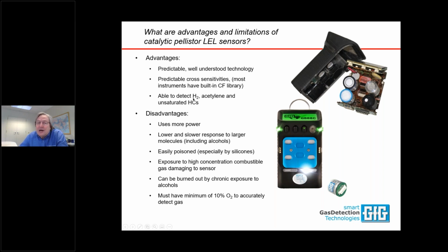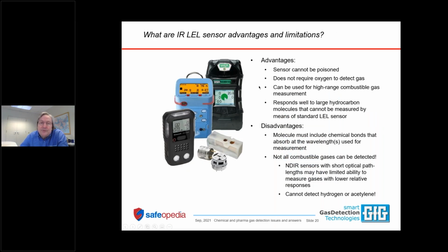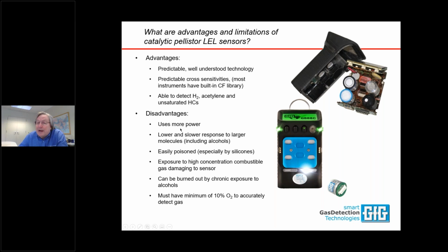It's able to detect hydrogen, acetylene, and unsaturated hydrocarbons in general, all those olefins and aromatics of interest. Disadvantages: the catalytic sensor uses more power than the other sensors. It has a lower and slower response to larger molecules, including alcohols. It can take up to 5 minutes for the catalytic sensor to reach its final, completely stable 100% T100 reading. It can take 5 minutes to get there for something like ethanol. That's a pretty slow rise.